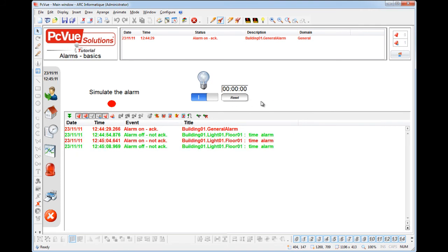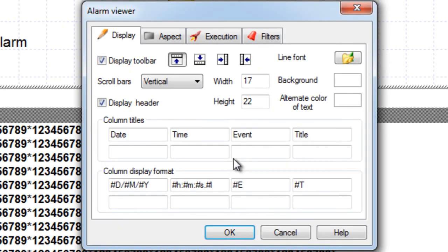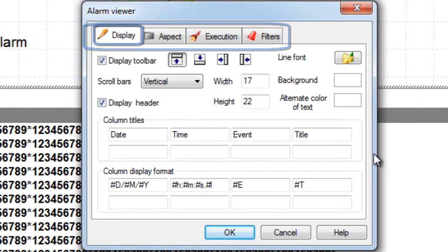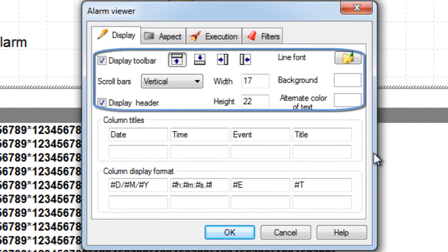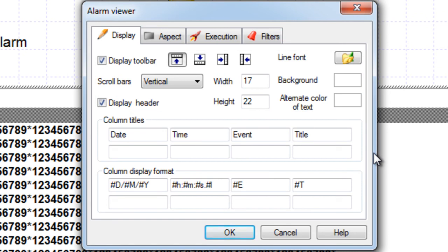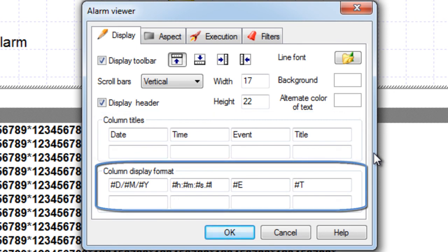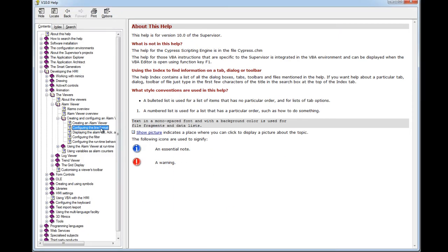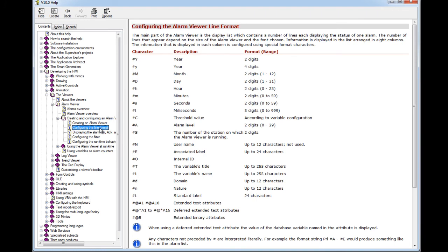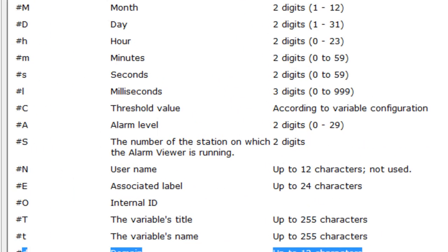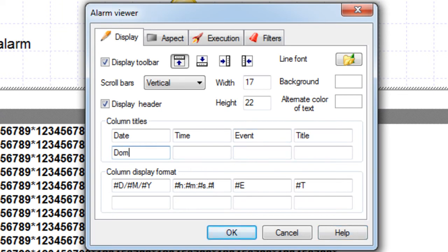The alarm viewer is fully configurable. In design mode, double-click the alarm viewer to access the properties — four tabs appear. The display tab is used to configure general display settings. The alarm viewer can display a maximum of eight columns with fully customizable content. You can configure the column title and display format using substitution characters. Click the Help button to access the online help within PcVue — the topic to look up is 'configuring the alarm viewer line format', which shows all format possibilities. For example, we can add a substitution to display the domain, entering the title 'domain' and the substitution '#D' to display the domain.